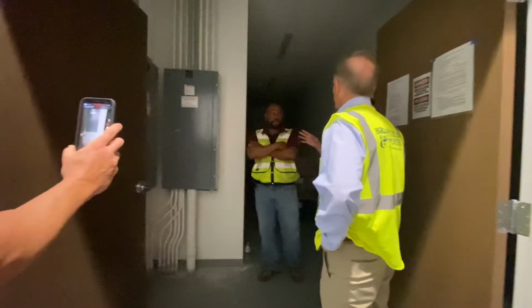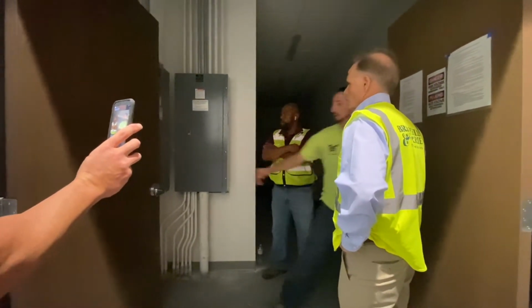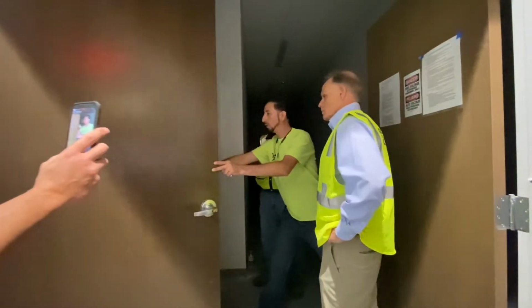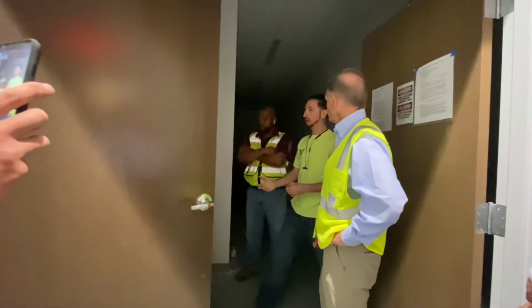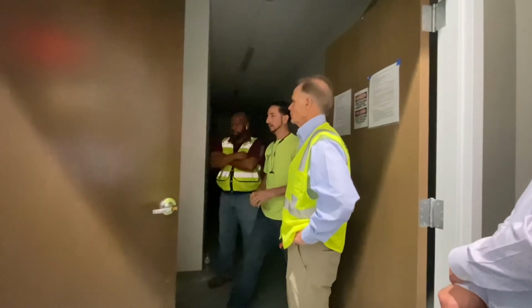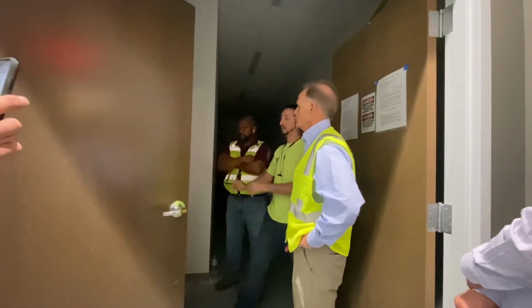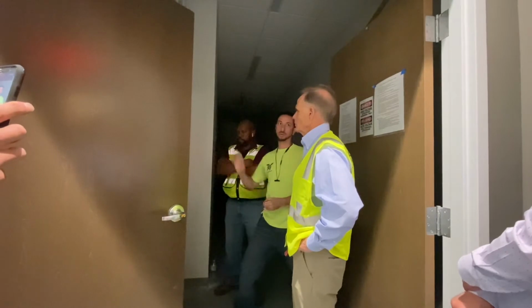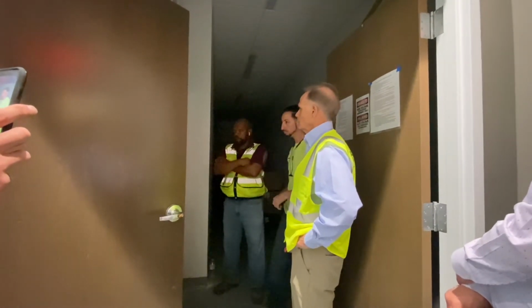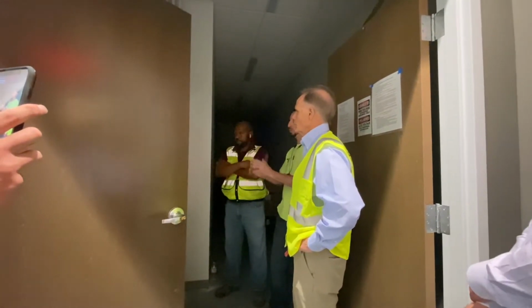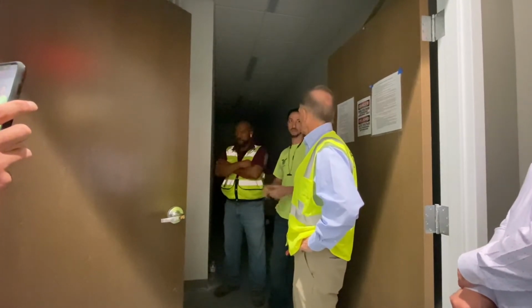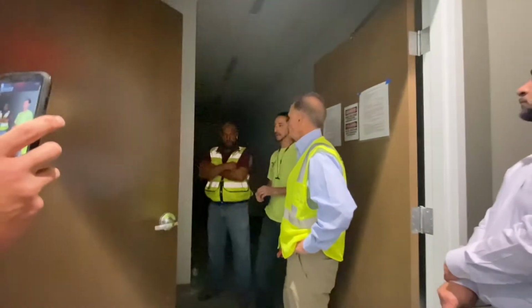This panel also has a processor associated with it. Basically, all the processors for the whole building are on a network together. There's a head-end processor in the data room, and anytime programming needs to happen, that can happen at the head end, and it will send all that information through the network to the associated processor. So you don't have to literally go to every single one to dump a program in or reconfigure something - you can do it from the head end.